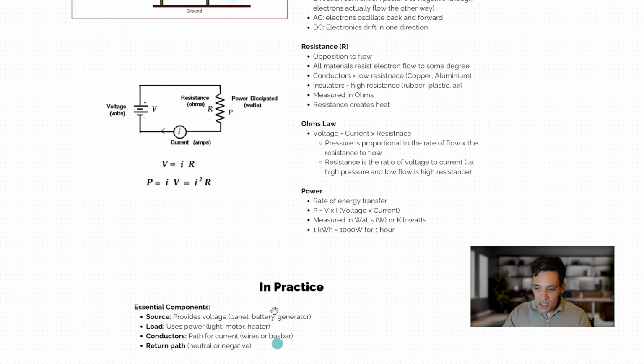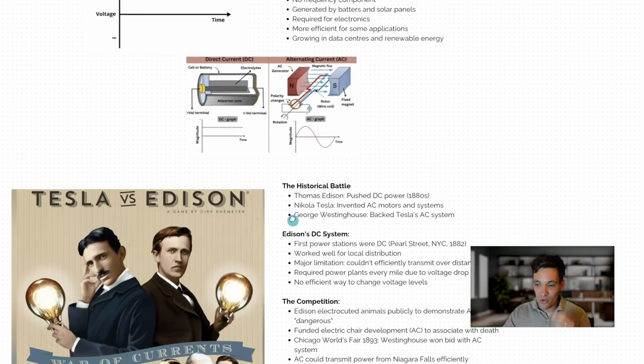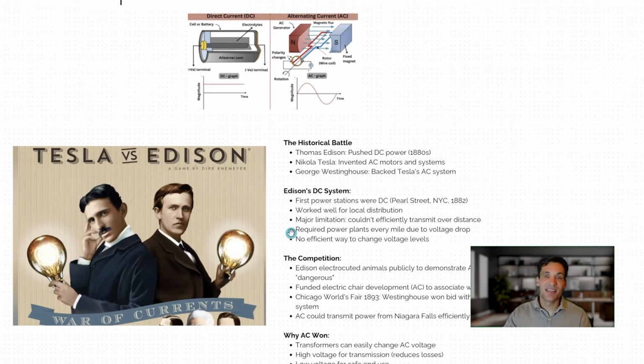So to efficiently transmit power across distances, you need to step up the voltage. Instead of transmitting at 200 volts, you need to transmit at 20,000 volts or 60,000 volts, depending on how far you're transmitting. The problem with DC electricity is that back when these systems were being designed, in the late 1800s, there was no easy way to step up DC voltage. Now we can do it with rectifiers and power electronics, but they are relatively recent advancements.